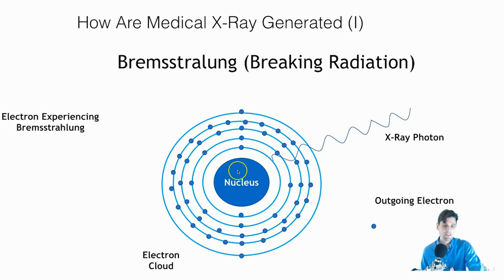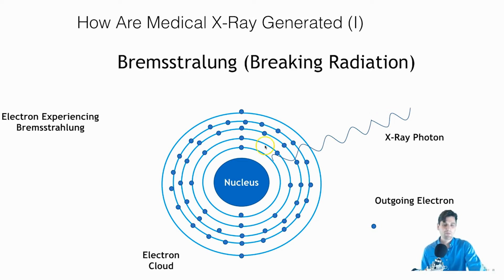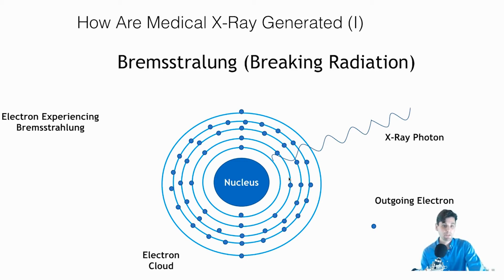In order to conserve momentum, an x-ray photon is ejected. If the electron comes out in one direction, the x-ray photon will come out in the opposite direction. This happens in a continuous manner: an electron could be steered just a small amount by the nucleus, in which case a very low-energy x-ray photon is emitted; or the electron could deposit nearly all of its energy into the x-ray photon. This means there's a smooth, relatively continuous spectrum of possible energies that can be generated via Bremsstrahlung radiation.